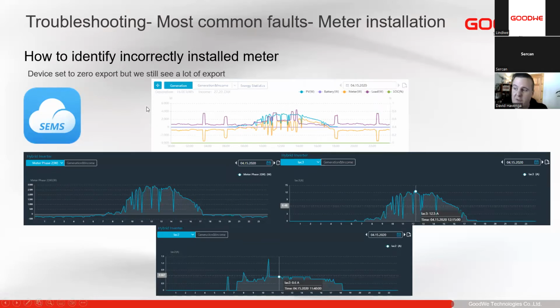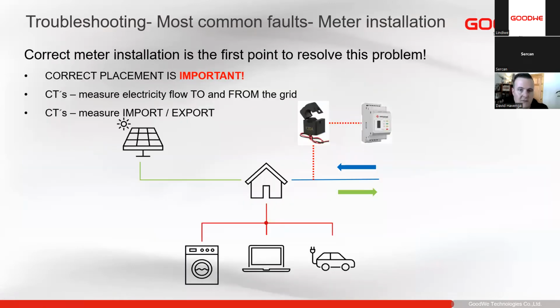So it's very important to make sure our meter installation, the wiring to the meter, is the same as the inverter's wiring. So correct CT placement is very important for us as well.